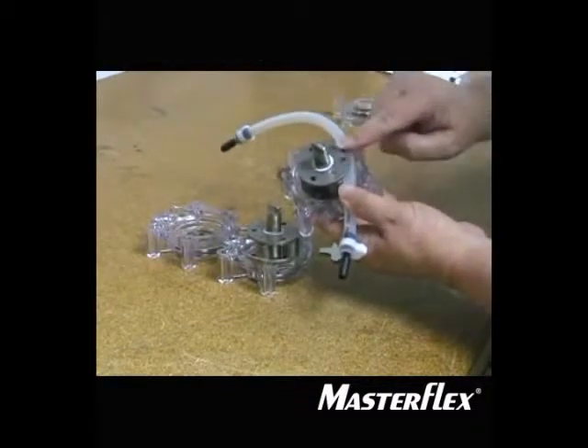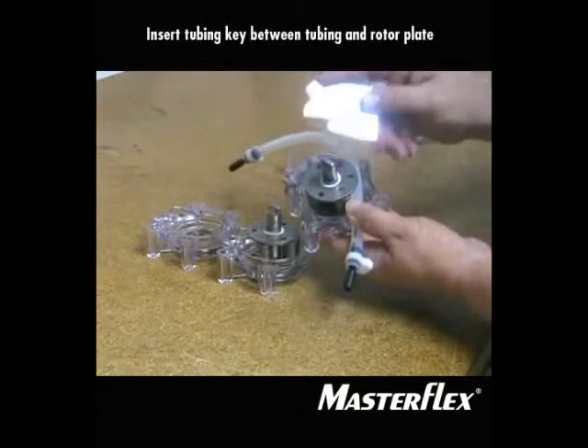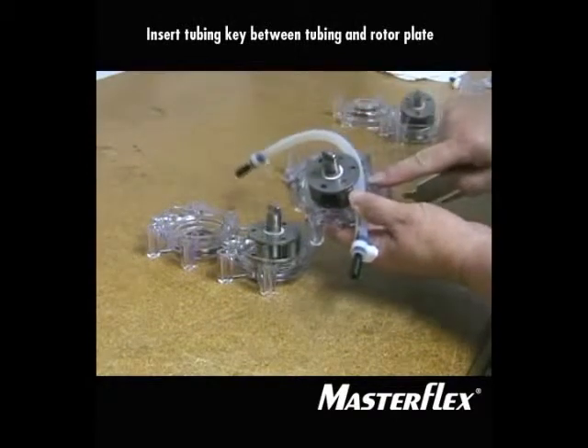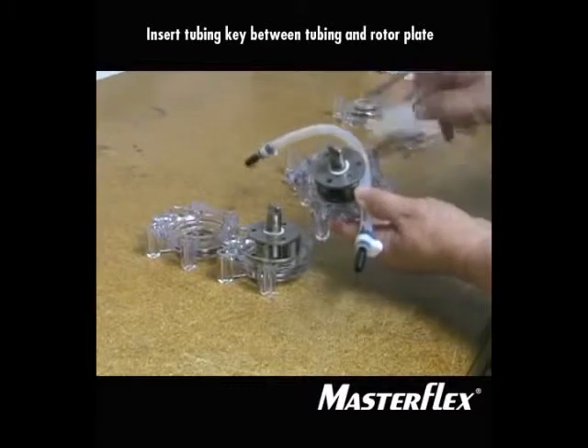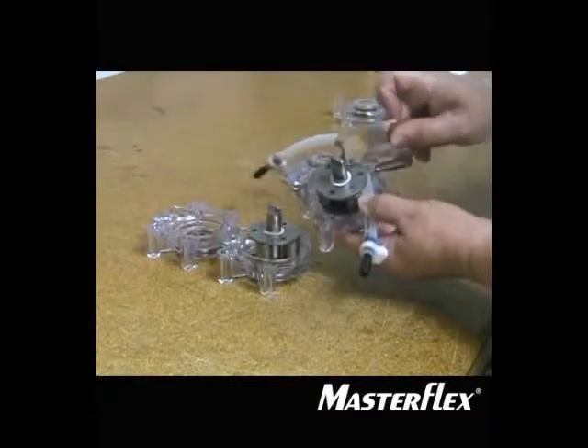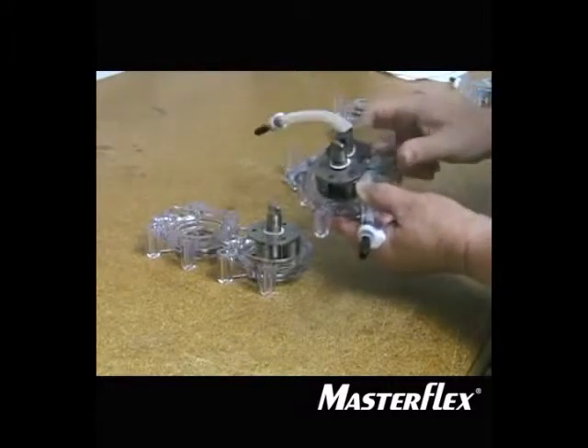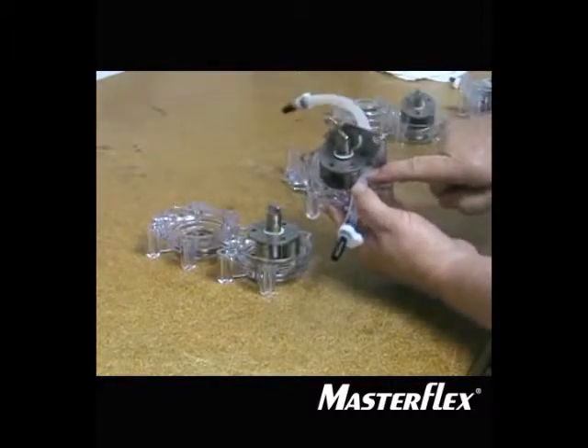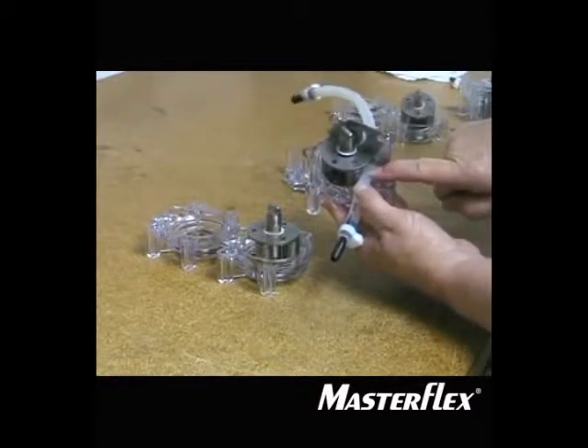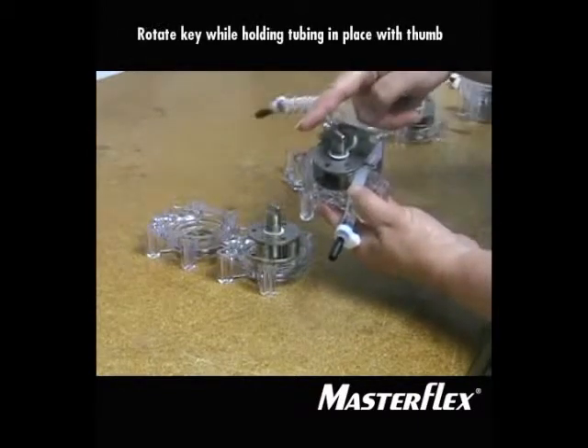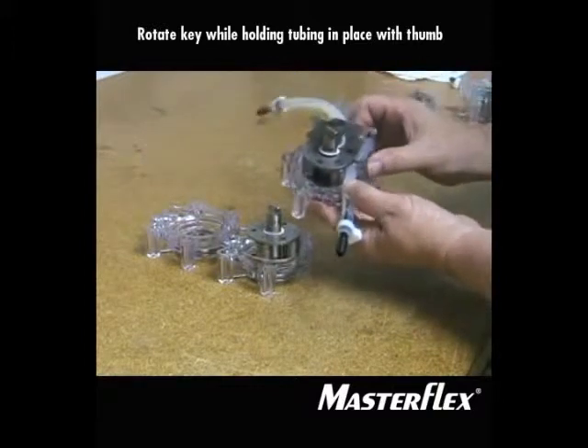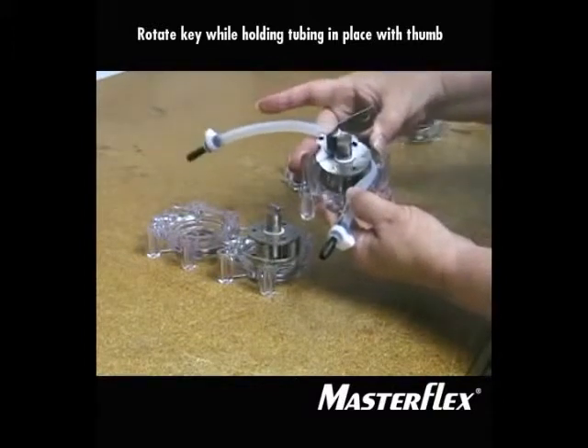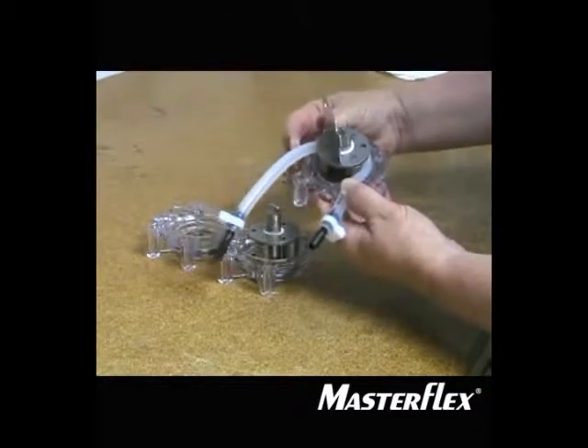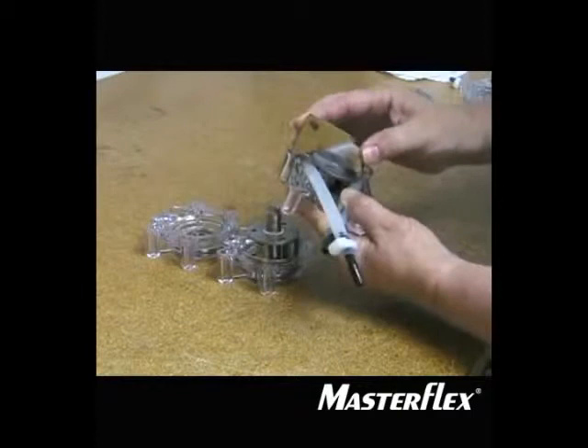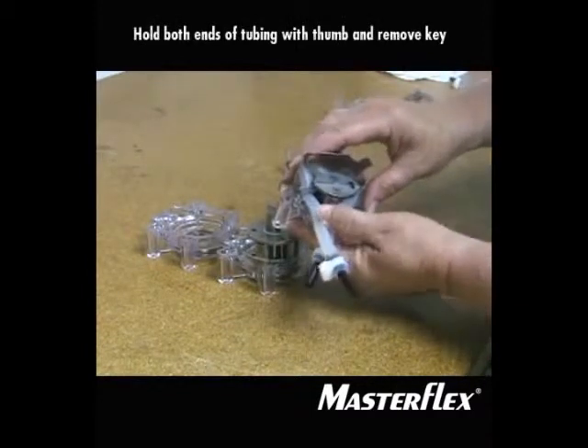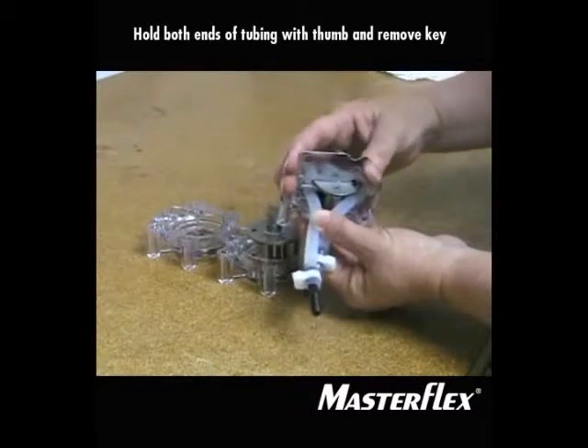Rest it against the first two rollers. I'm going to take this tubing key and I'm going to insert it between the tube and the rotor plate, like so. Notice how the key presses the tubing into the housing. Now I'm going to start turning this key all the way to the other side while holding the tubing in place with my thumb. I'm going to use the key. It's going to press the tubing uniformly into the pump. Now I'm going to move my thumb over slightly. I'm going to remove the key.